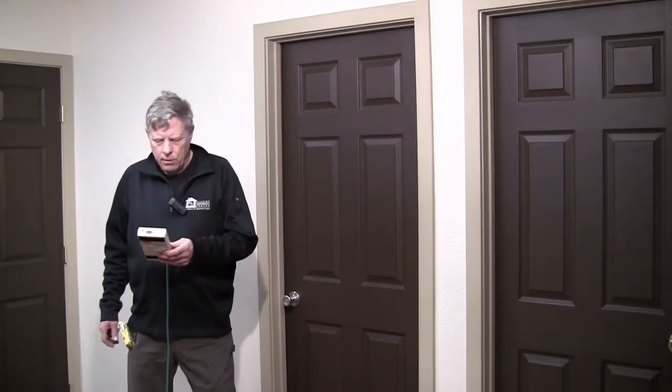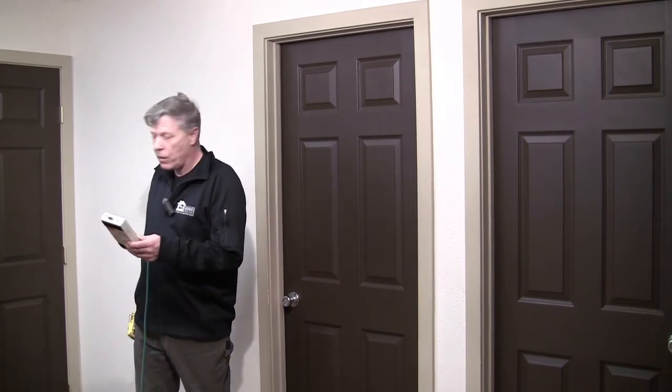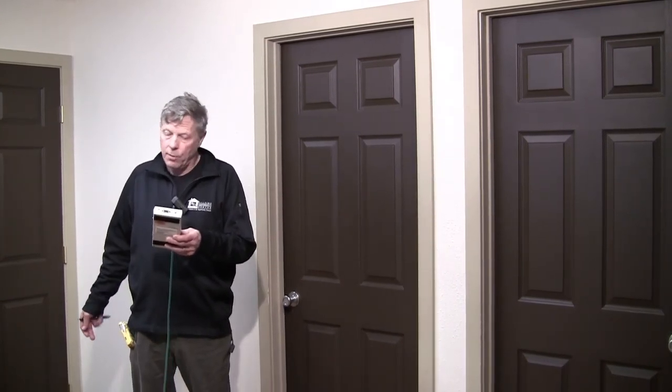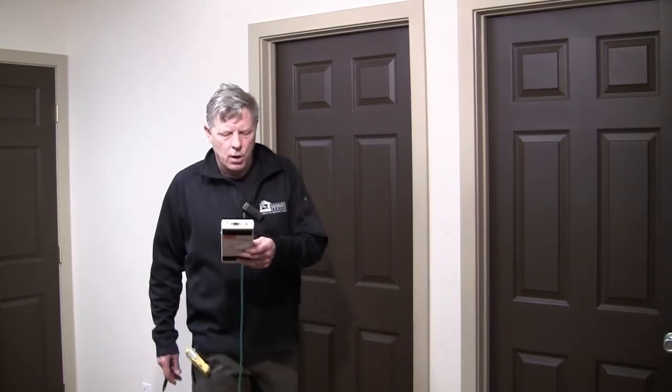and again it's negative 7.6, so that door must have a pretty good undercut under it also because it hasn't changed our pressure at all. Alright, so now we're at the worst case pressure for line, let's see, it's negative 7.6. And so we're going to leave that door closed. That would be 5D. So we're now in the worst case setup, and this is the pressure we're going to be using when we test the water heater and furnace for spillage on line 7.